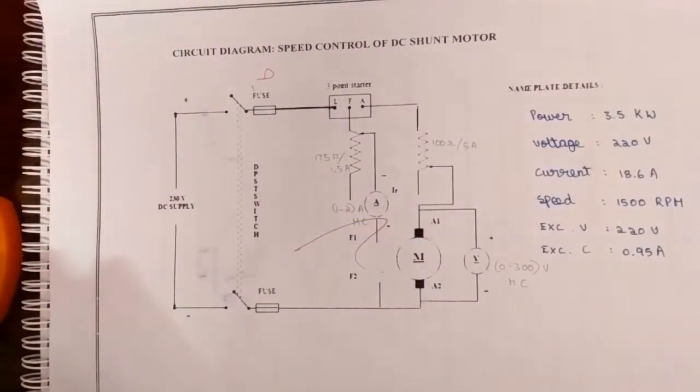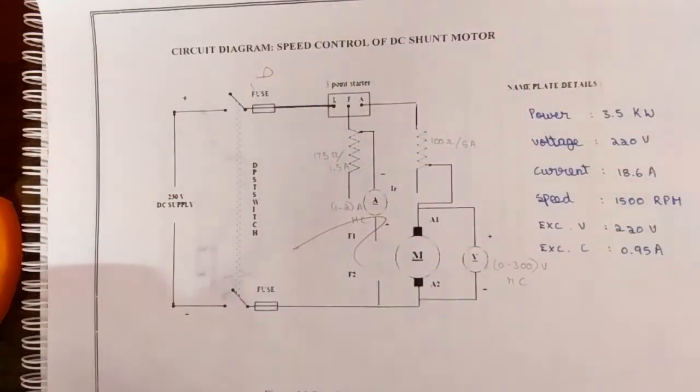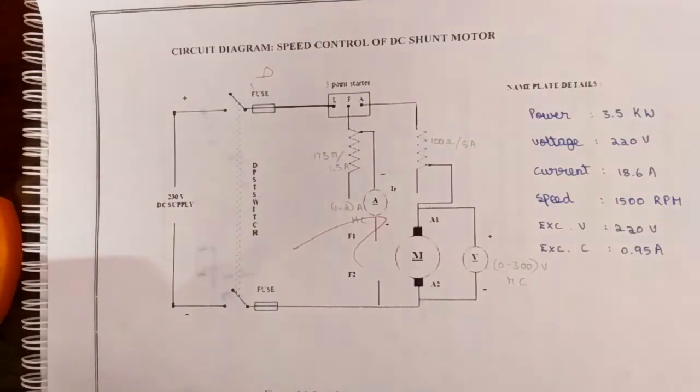Before moving to the procedure, first the precautions we should take care is that the fuse is selected in such way that its rating is 120% of the no-load current. The spring balance should be kept at zero position throughout the experiment. The motor field rheostat should be kept at minimum position at the time of starting.